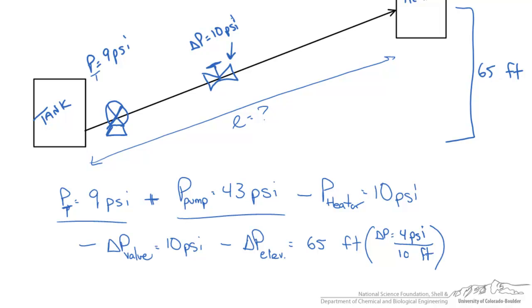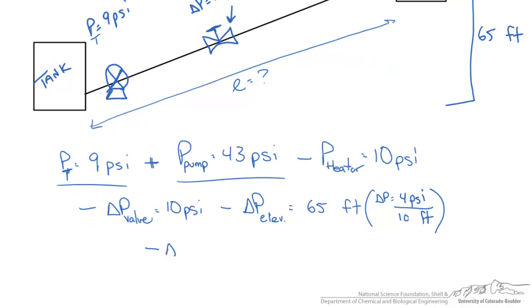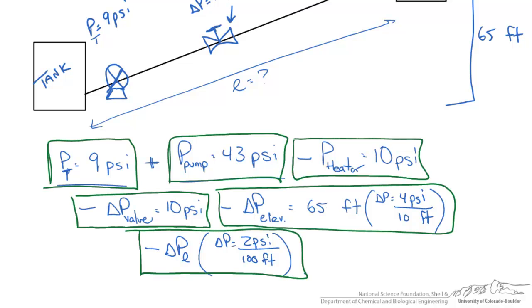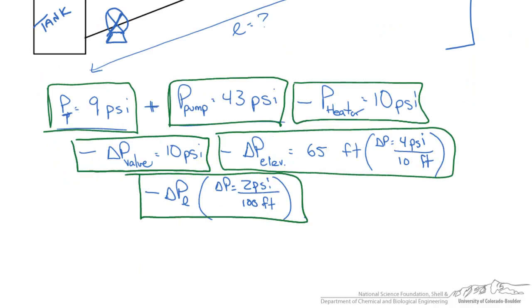Lastly, we're going to subtract our delta p of the length of the pipe, which also has a relationship: delta p is 2 psi per 100 feet of pipe.